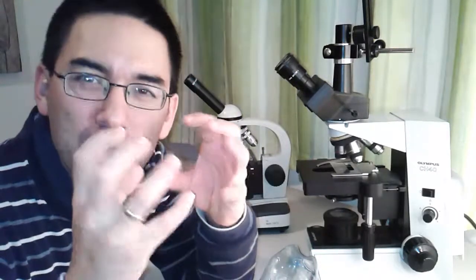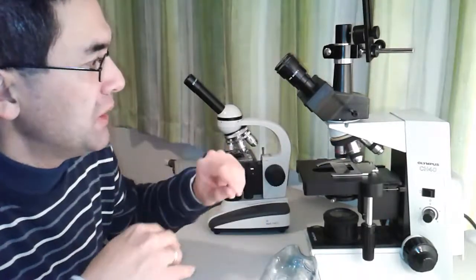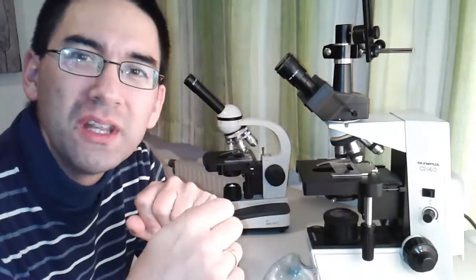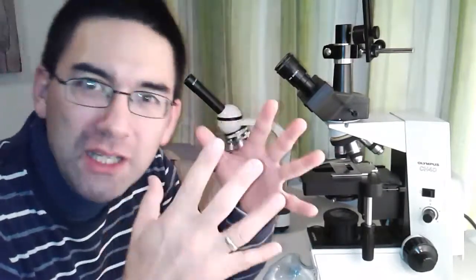Dust is a problem for a variety of reasons. It not only disturbs the image quality when you make a picture, but it can also be harmful for the optics. When dust collects on the optics and parts, then also when you clean the optics, the dust might scratch the surface. And over the years, when dust collects in the gears of the microscope and in the focus knobs, there is oil in there and this will solidify, making the focus knobs difficult to turn. So dust is a problem for many reasons.